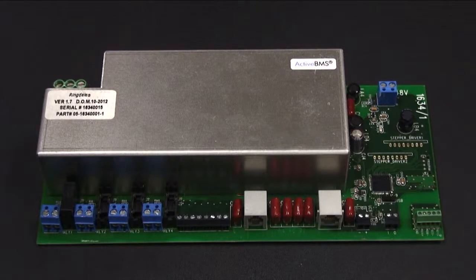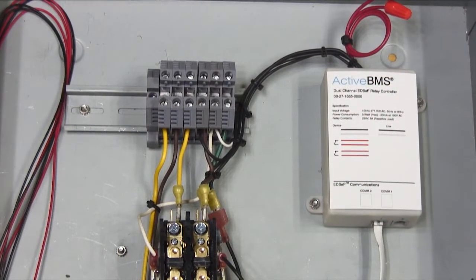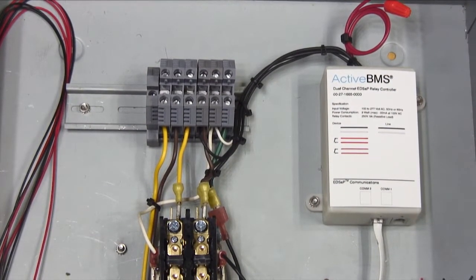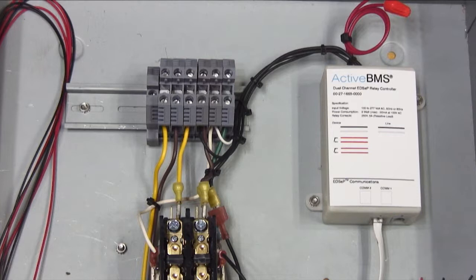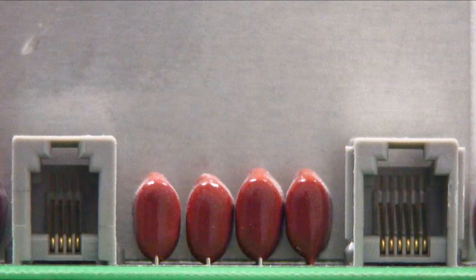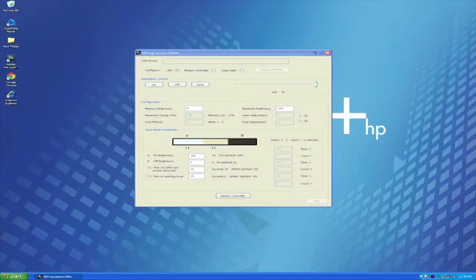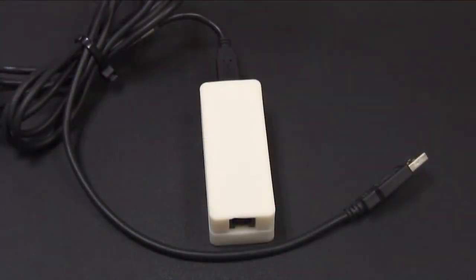The 4-relay controller also has a 0 to 10 volt output to allow dimming of legacy lighting devices or to control valves or variable speed fans that have a 0 to 10 volt input. A smaller 2-relay controller that can be controlled directly from an LSC or an LSM that can be wired directly into a junction box is also available. All relay controllers can be locally managed through their EDS-AP port using a laptop or PC with application software and a USB dongle, or centrally managed through an LSC.